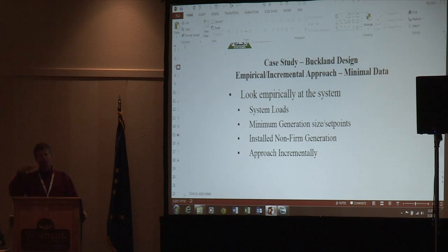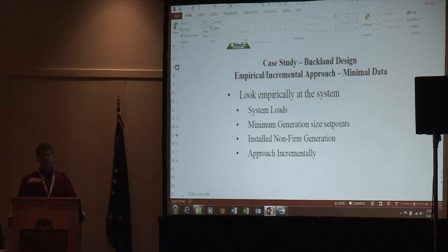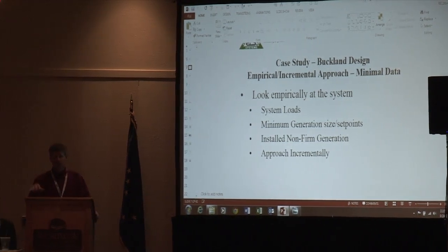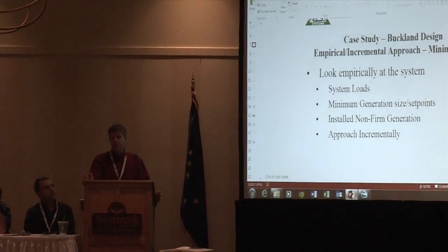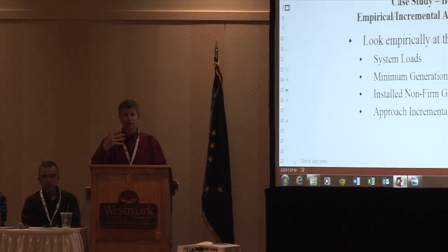What we do to try to maximize the wind is let the wind go, get as much energy as we can out of it, and back the diesels down while regulating frequency until we reach what we call a minimum diesel set point. On a 450 kW unit, for example, that might be 200, 225, or 250 kW. That's a parameter the operators get some input on, but with experience they can modify it.